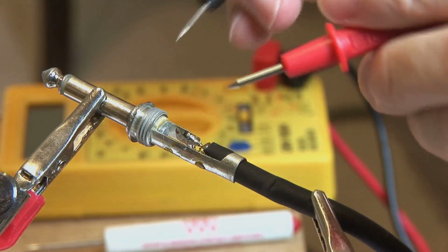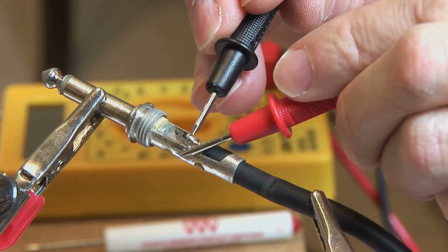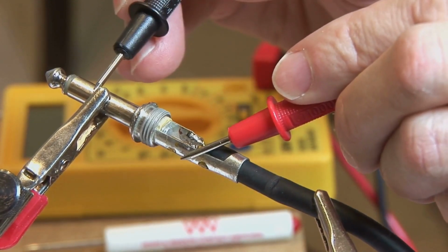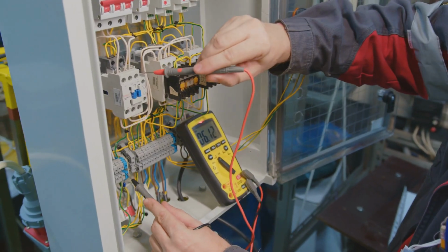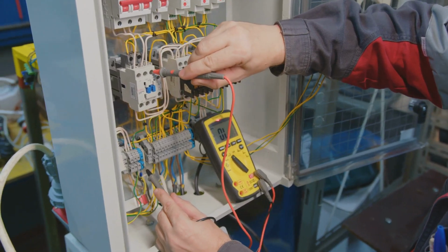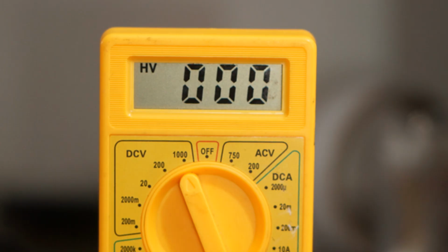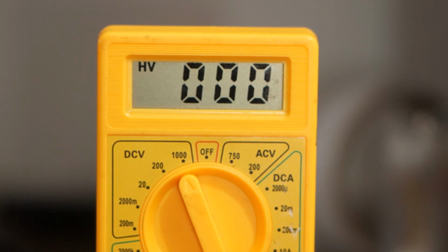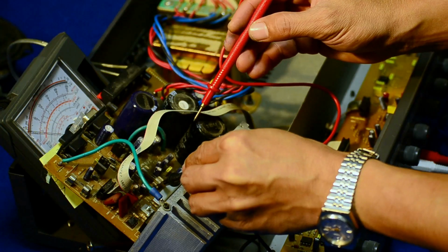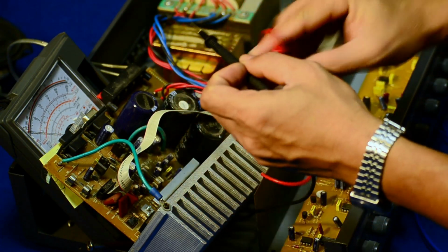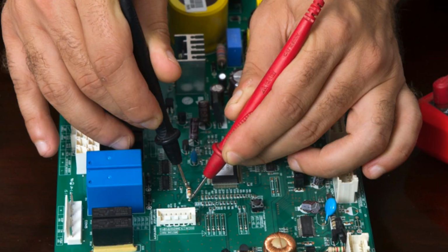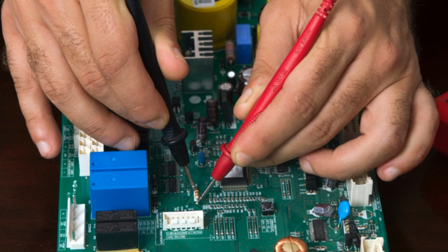Step 2. Connect one lead to one end of the component or wire you are testing and the other lead to the other end. Step 3. If there's continuity, the multimeter will beep or show a reading near 0. No continuity will result in no beep or a high resistance reading. Practical tip: when testing fuses, it's best to remove them from the circuit for accurate results. This avoids any parallel paths that may give false readings.